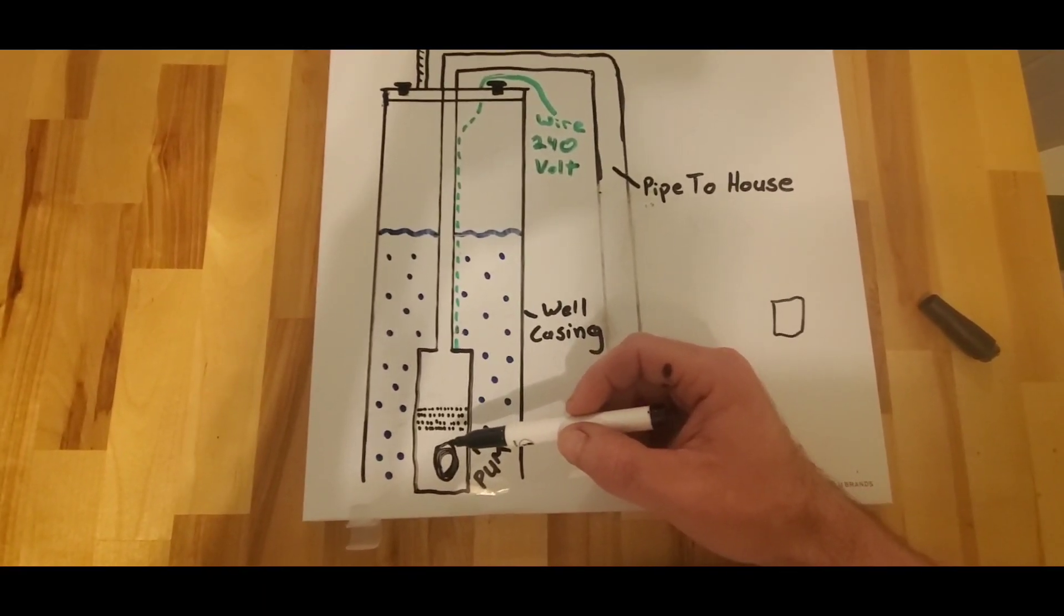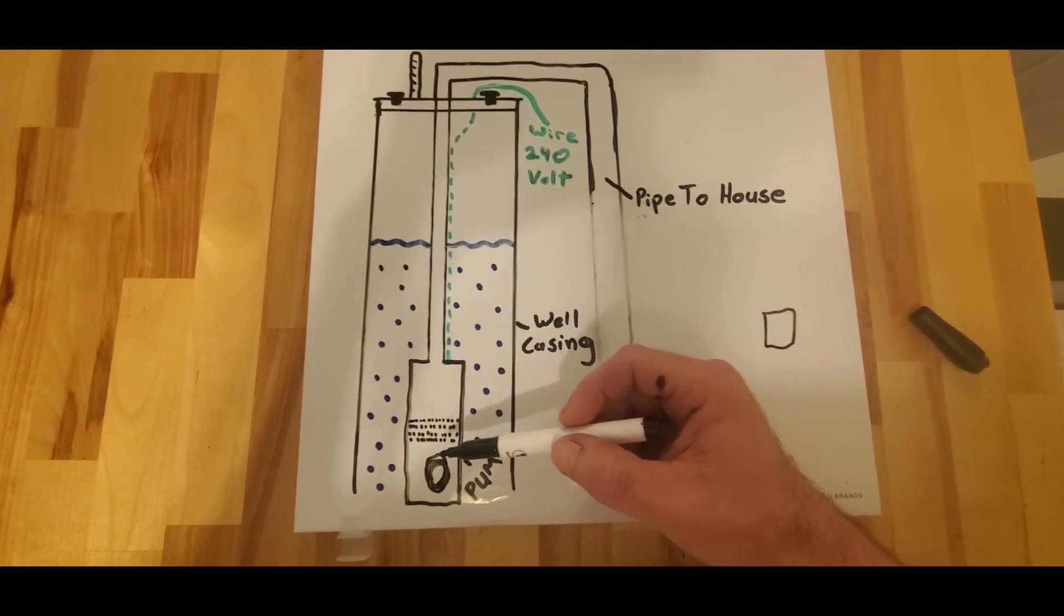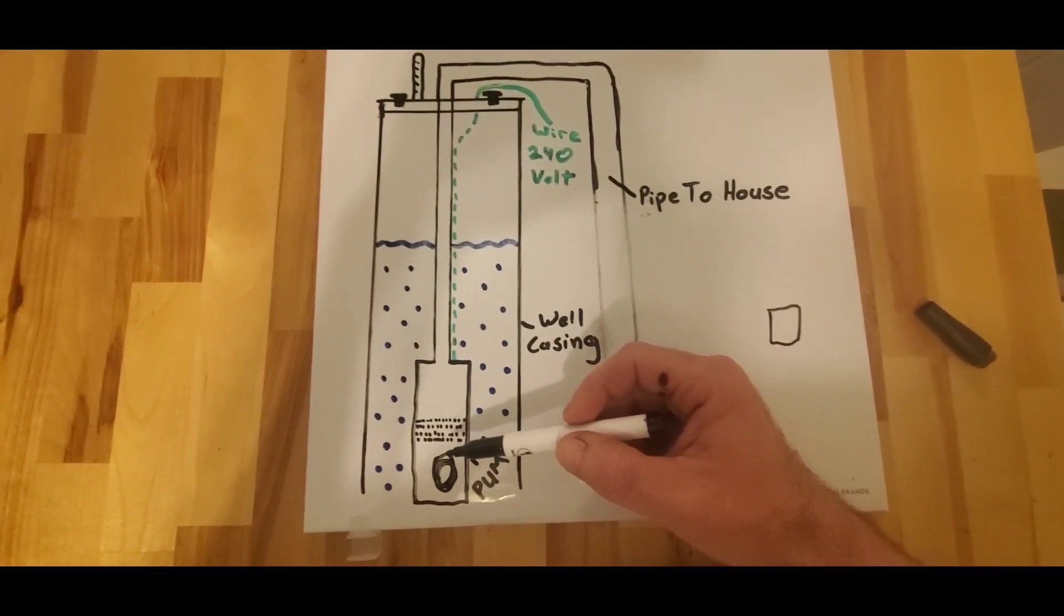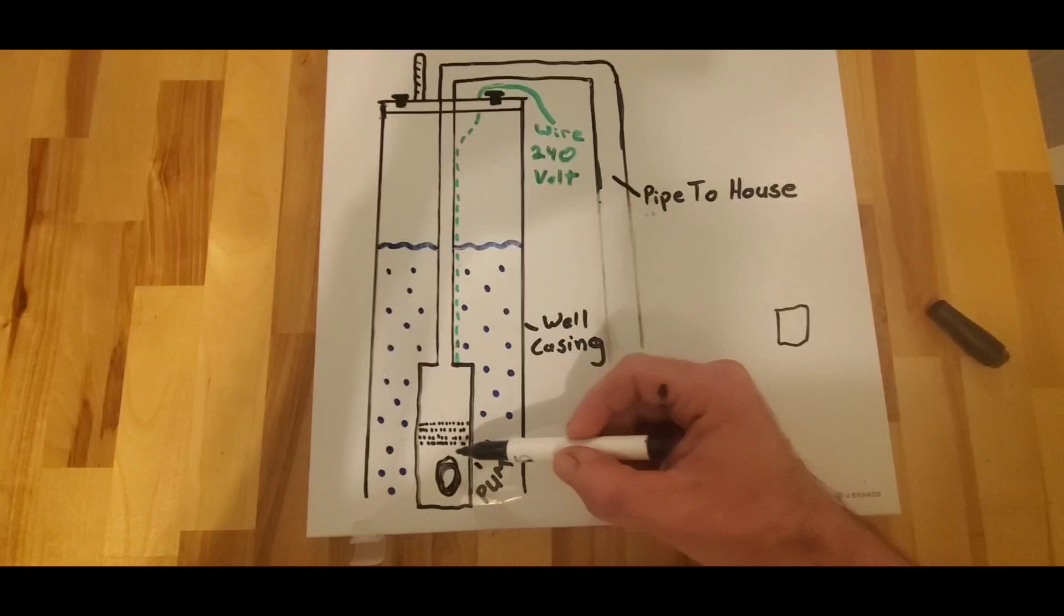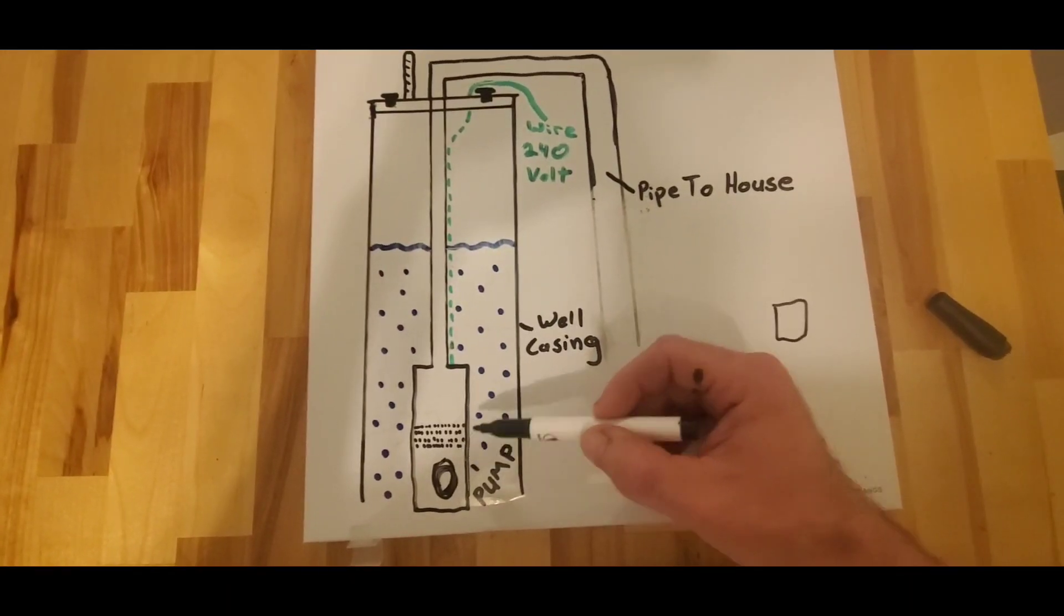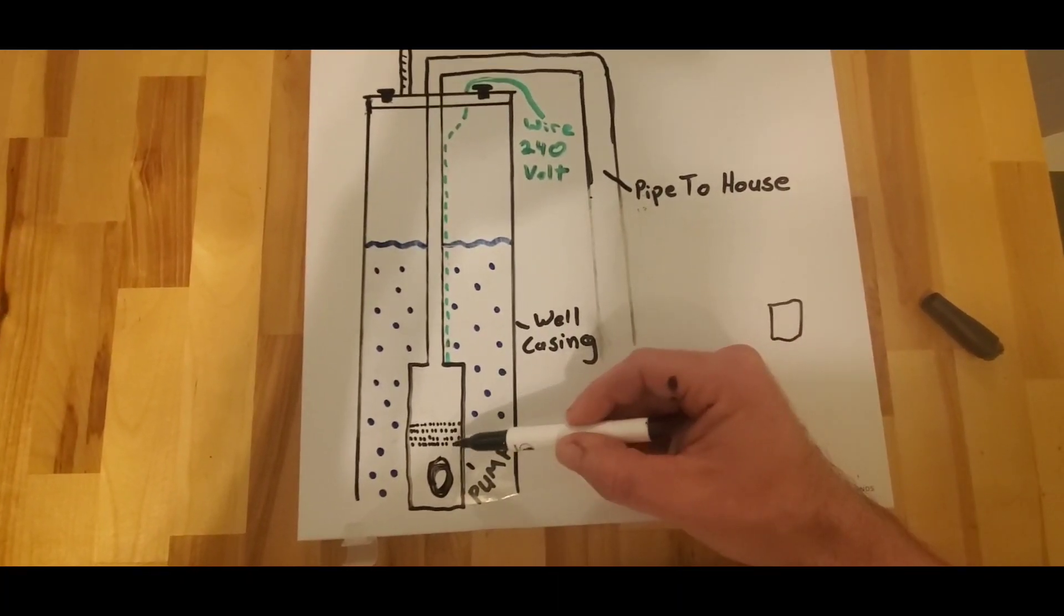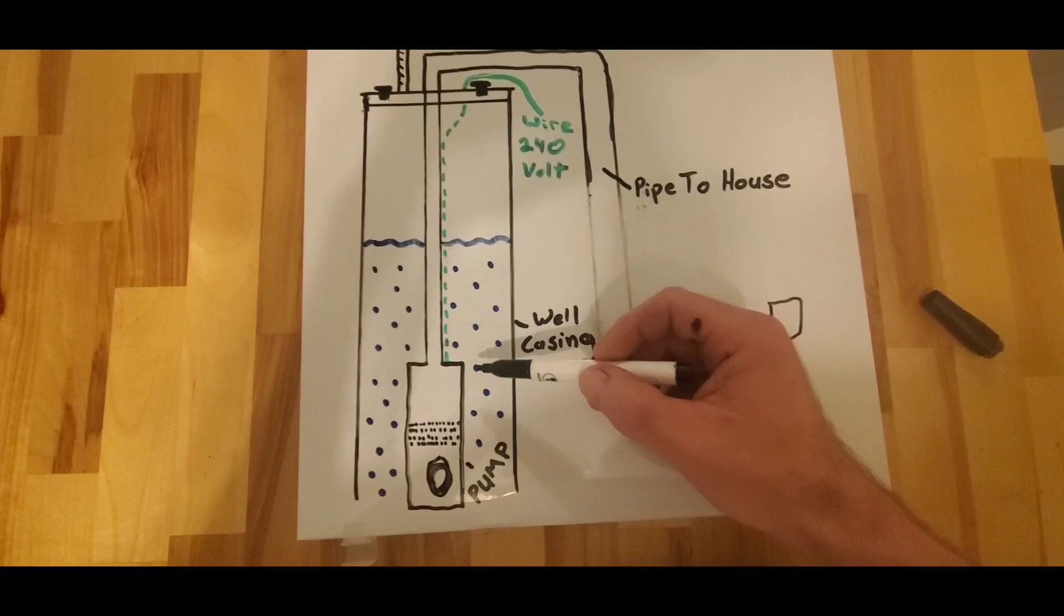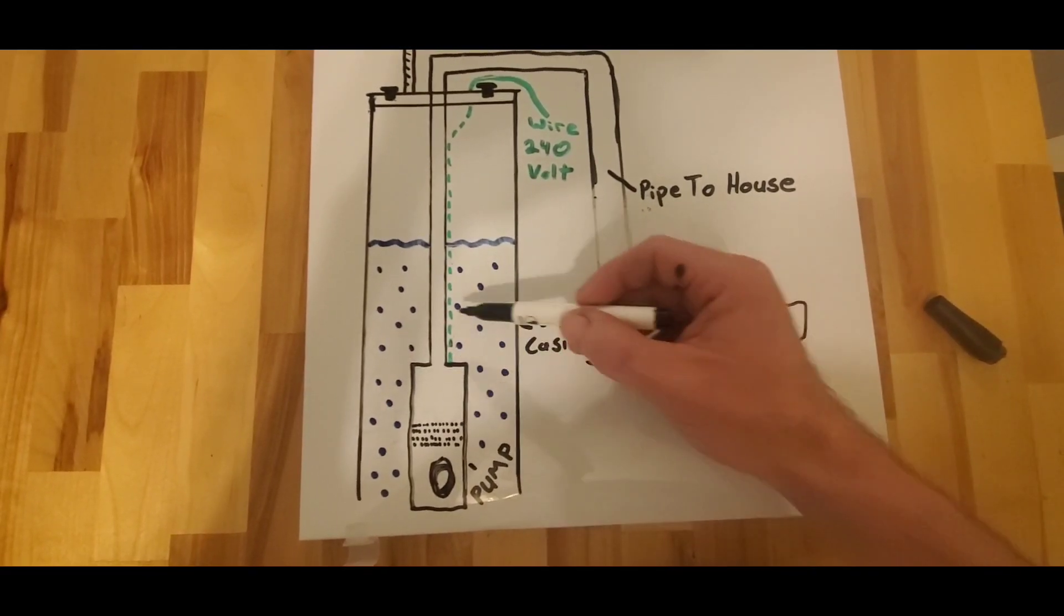Now you've been without water for a few days, and if you've left the breaker on, this is what has happened. Your electric motor has gotten so hot, it has transferred the heat into the water. Now the water in this area is 200 degrees.